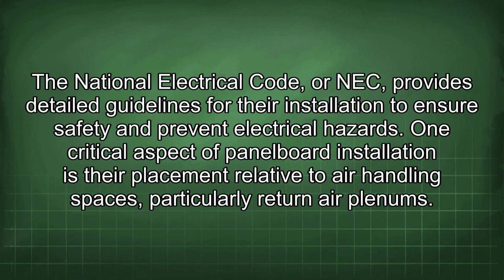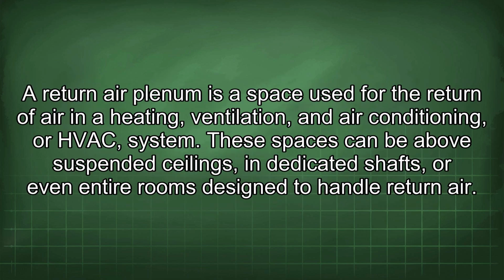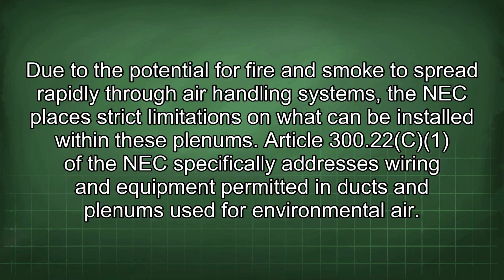The National Electrical Code, or NEC, provides detailed guidelines for their installation to ensure safety and prevent electrical hazards. One critical aspect of panelboard installation is their placement relative to air handling spaces, particularly return air plenums. A return air plenum is a space used for the return of air in a heating, ventilation, and air conditioning, or HVAC system. These spaces can be above suspended ceilings, in dedicated shafts, or even entire rooms designed to handle return air. Due to the potential for fire and smoke to spread rapidly through air handling systems, the NEC places strict limitations on what can be installed within these plenums.